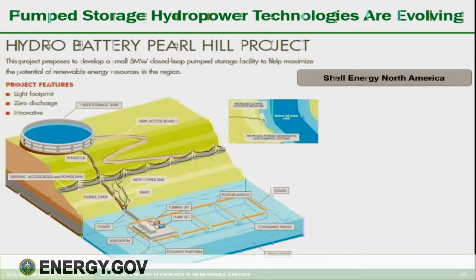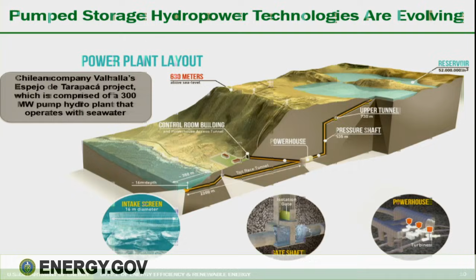Another fairly common technology paradigm we're seeing now is pump storage using seawater as the lower reservoir, which is what the Egypt and Saudi Arabia plants I was talking about are using. This is actually a diagram of a plant in Chile. Right now, using best available materials, these projects cost about 30% more than a standard pump storage plant because of corrosion. Working on materials that can reduce those costs is another potential critical research area. If we can get that right, it dramatically expands the geographic opportunities for pump storage, both in the US and across the world.